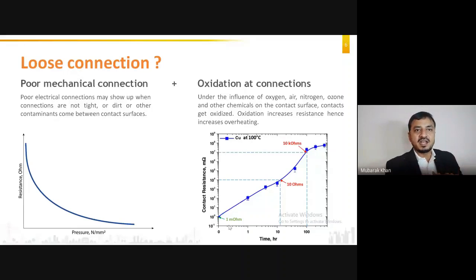Okay, so oxidation at the connections - copper is a very good conductor, copper oxide or cuprous oxide are not good conductors. When copper is exposed to atmosphere or the chemical environment, like under the influence of oxygen, nitrogen, ozone, or other chemicals reacting with the copper, this causes the formation of cuprous oxide. And because cuprous oxide is not a good conductor, if it comes between the contact surfaces, the contact resistance will definitely increase.